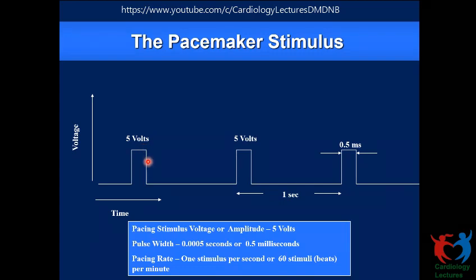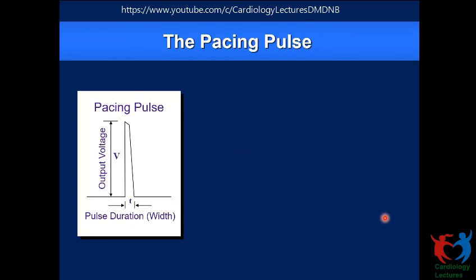And then the pacemaker, as you know, has a clock. It runs for 1000 milliseconds, and at the end of 1000 milliseconds, it delivers the next pulse, and so on. And this is the amplitude, and this is the pulse duration, and the duration of time between 2 pulses is the rate at which you are pacing the heart in terms of time. In this case, it's 1 second, in other words, 1000 milliseconds. I'm sure you know this. I'm just putting it in context.